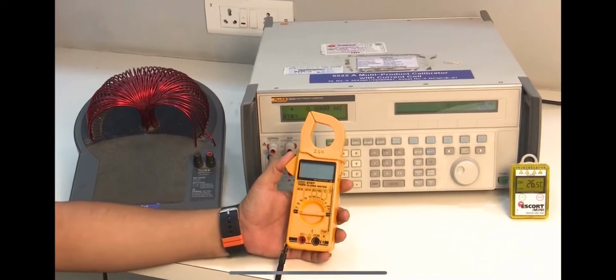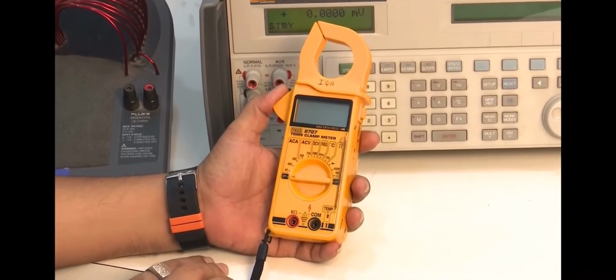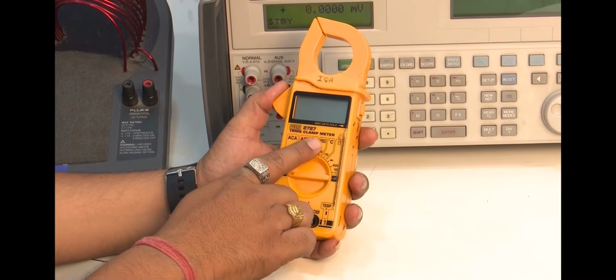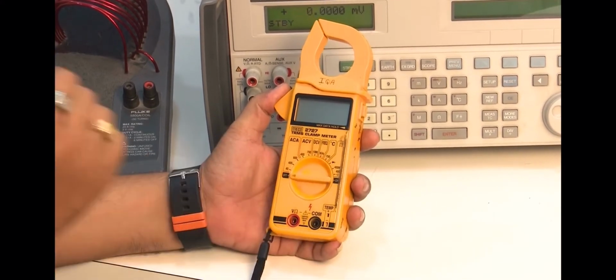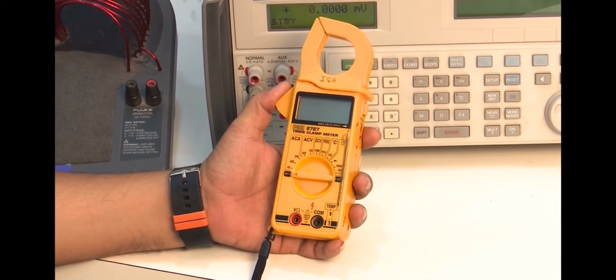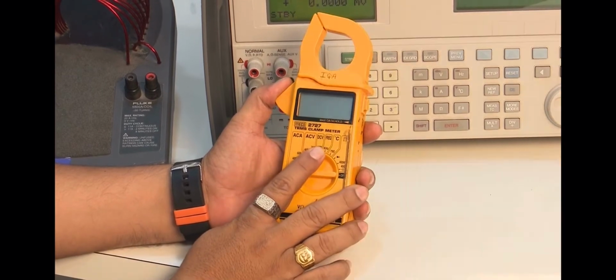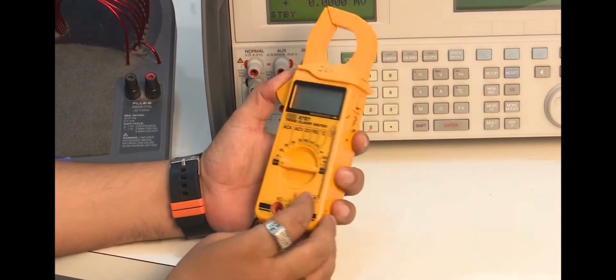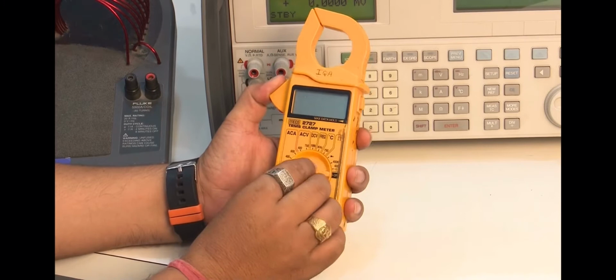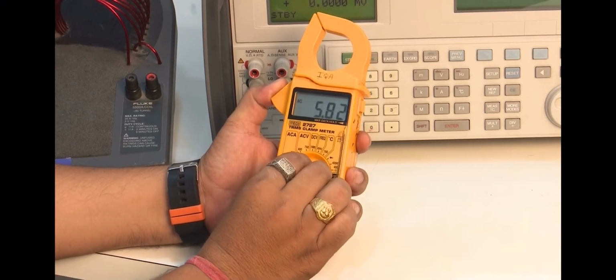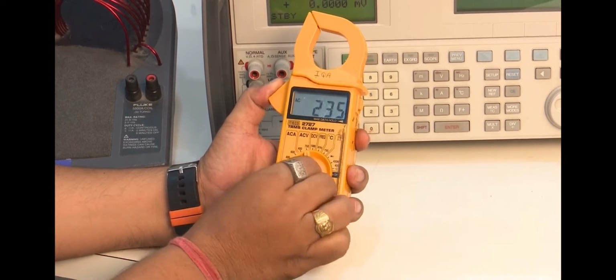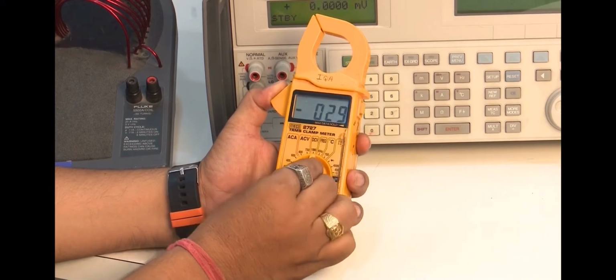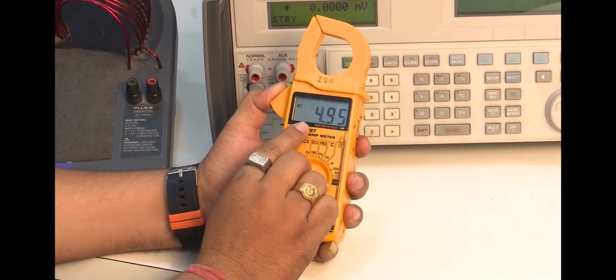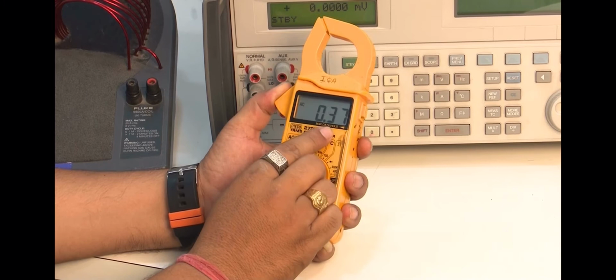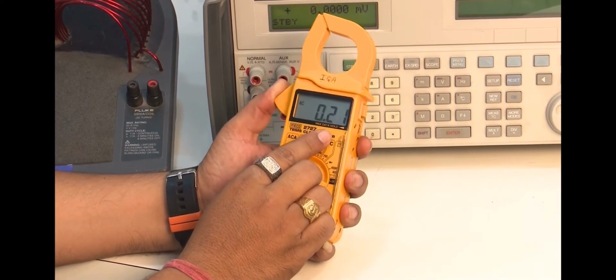Here I am demonstrating live display of step-by-step calibration method of digital clamp meter, similar to multimeter calibration, as per Euramet CG15 guidelines. After cleaning, visually inspect the clamp meter for free movement of rotating parts, display and proper working of all functions.